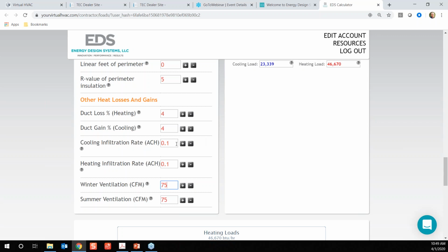And at first I didn't do that. When I did my previous load calcs, the defaults were 0.6 and 0.8. And all I did at my house is I said, okay, well, I've got fresh air, so I'm going to bump mine down to 0.4 and 0.6. And that's how I ended up with a 3-ton system at my house. So 32,000 BTUs, basically a 3-ton system. But if I was to do my load calc again, I definitely would go lower on those infiltration rates. And I probably would be able to put a 2-ton system in.